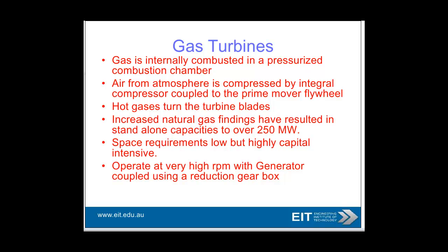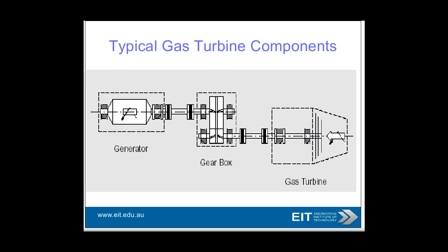Gas turbines: hot gases turn the turbine blades. You can go up to a standalone capacity of 250 megawatts. Space requirements are low, but it is highly capital intensive, quite an expensive bit of hardware. Very high RPM. You can hear the shriek of the gas turbine, with the generator coupled using a reduction gearbox. Typical gas turbine: turbine here, gearbox, and then your generator. So gear down here.